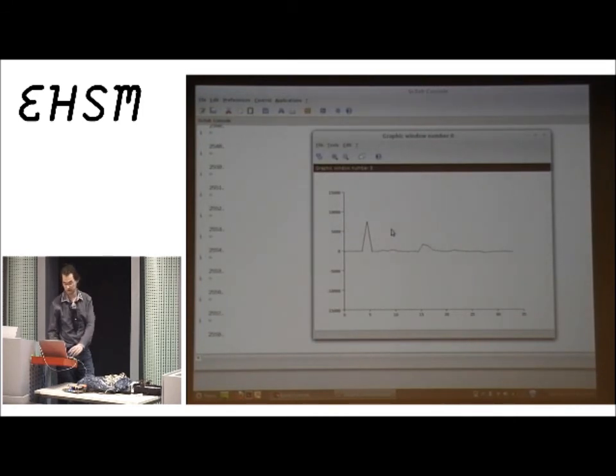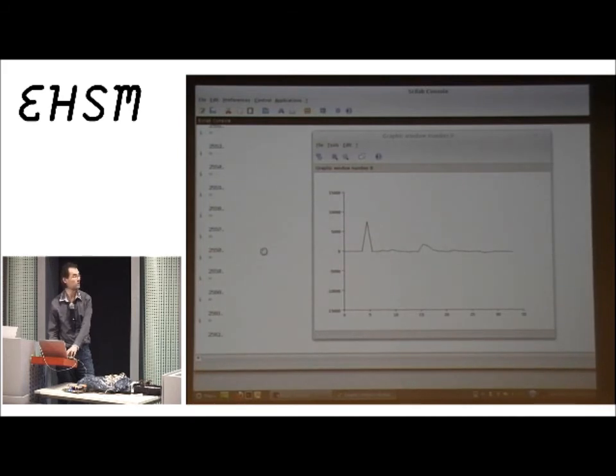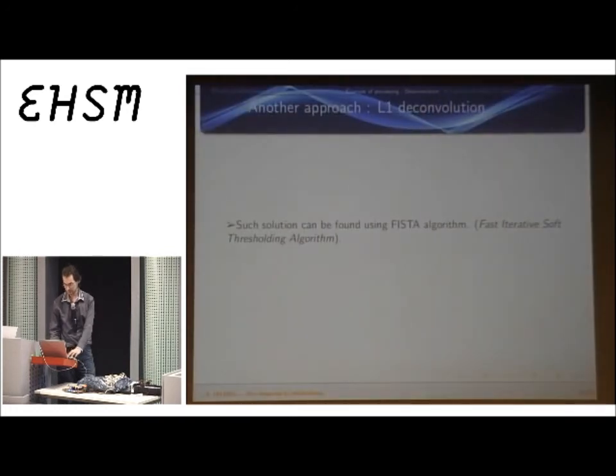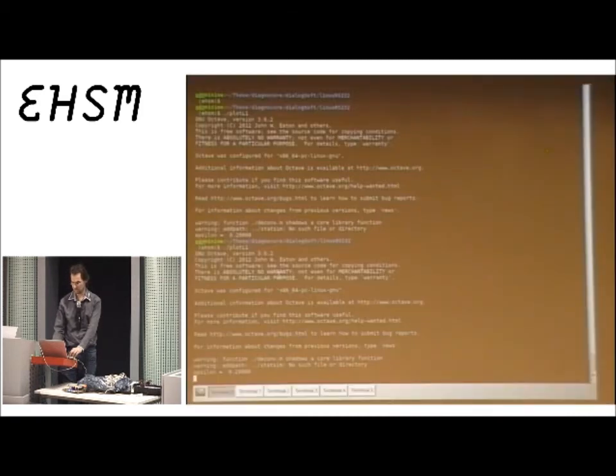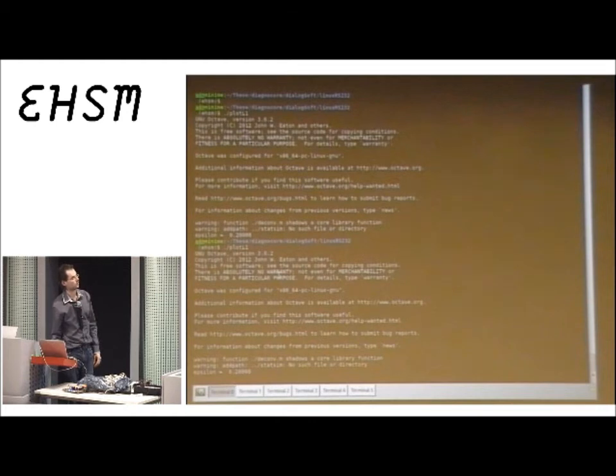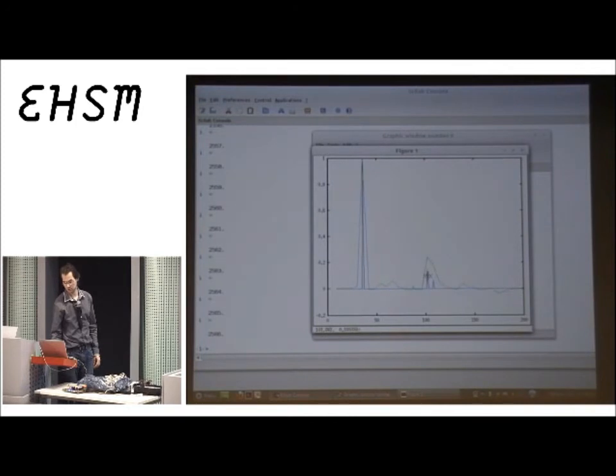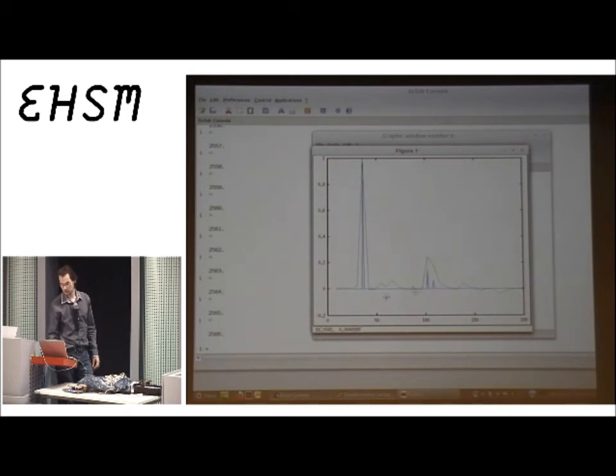The CLEAN algorithm allows a more precise location and can be simply implemented on many architectures. With the L1 deconvolution, the first peak is a bit higher, making it more likely to represent the true end of the cable. For automatic location, the locator takes this biggest peak and computes the distance between the injection point and the fault.